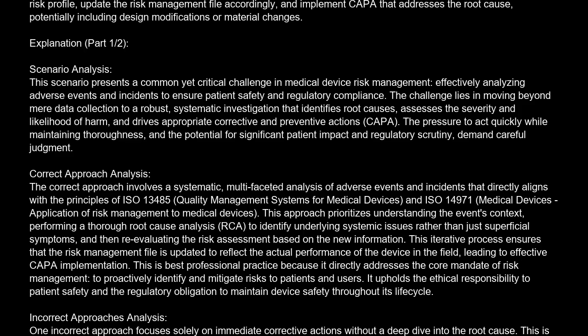careful judgment. Correct approach analysis. The correct approach involves a systematic, multifaceted analysis of adverse events and incidents that directly aligns with the principles of ISO 13485, Quality Management Systems for Medical Devices, and ISO 14971, Medical Devices Application of Risk Management to Medical Devices. This approach prioritizes understanding the event's context, performing a thorough root cause analysis (RCA) to identify underlying systemic issues rather than just superficial symptoms, and then re-evaluating the risk assessment based on the new information. This iterative process ensures that the risk management file is updated to reflect the actual performance of the device in the field, leading to effective CAPA implementation.